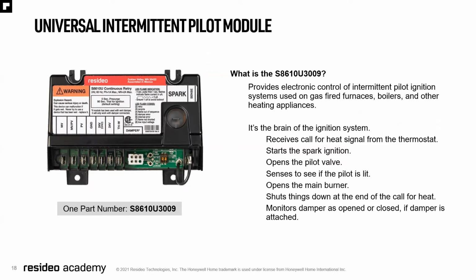Takes a call for heat directly from the thermostat. It starts the spark for ignition, at which point it should open the pilot valve. Rectification is used to prove if the pilot is lit. If the pilot is indeed lit, it will stop the spark, open the main burner, and the call for heat begins. At the end of a call for heat, everything shuts down.